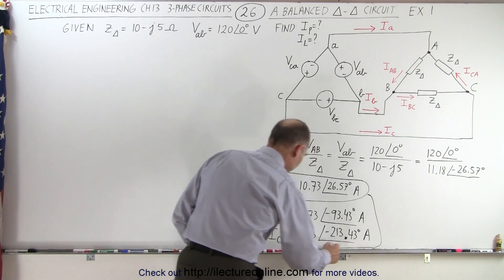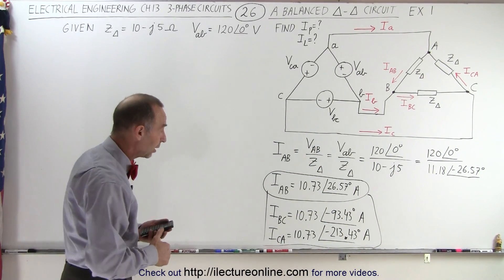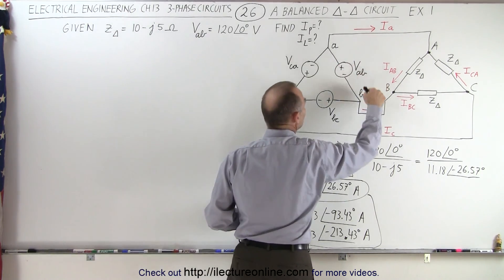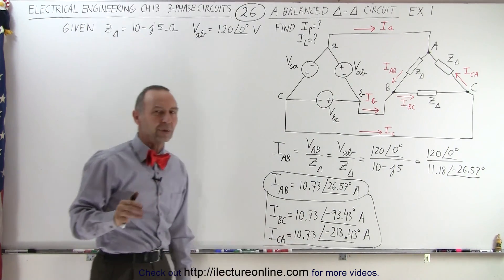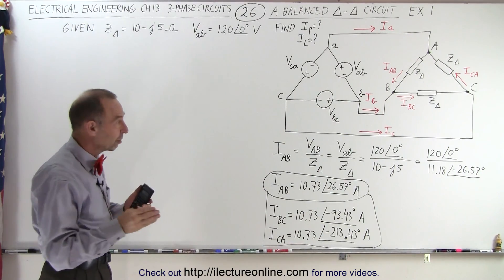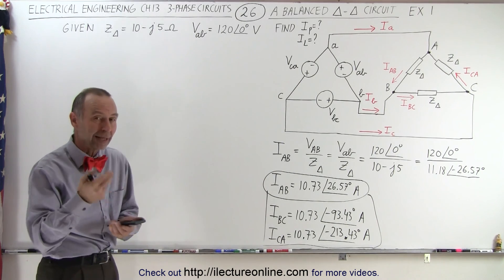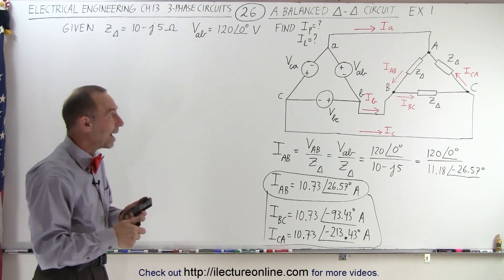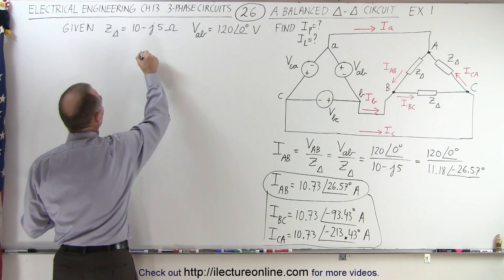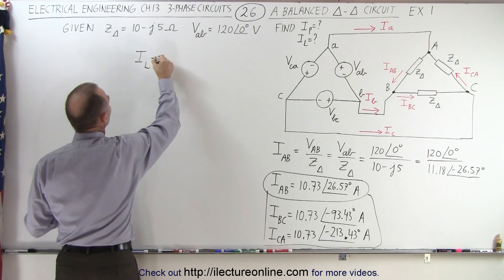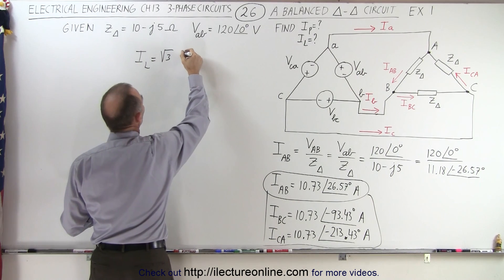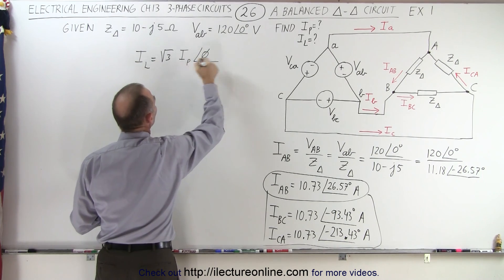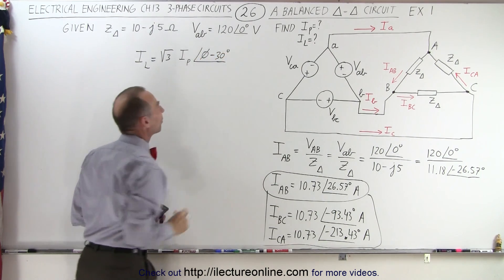Those are the three phase currents through the three load branches. Now we want to find the line currents Ia, Ib, and Ic. Just like with a Y-delta circuit, the line currents lag the phase currents by 30 degrees, and the magnitude is the square root of three times the phase current. In other words, the line current equals the square root of three times the phase current magnitude, with the phase angle of the phase current minus 30 degrees.